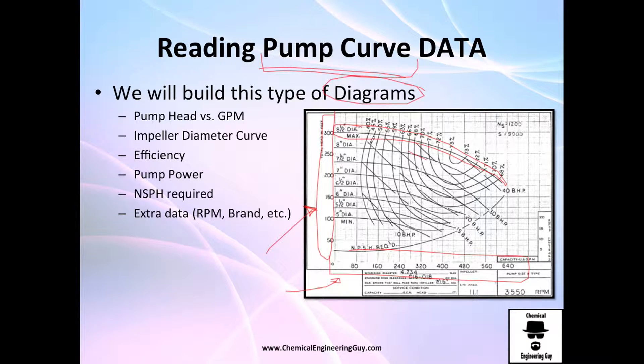We're going to see that we can do many of them for each size of impeller. And why is this? Because the smaller impeller, the less amount of fluid you're going to operate, and therefore you're going to have less head, less power, and all that.